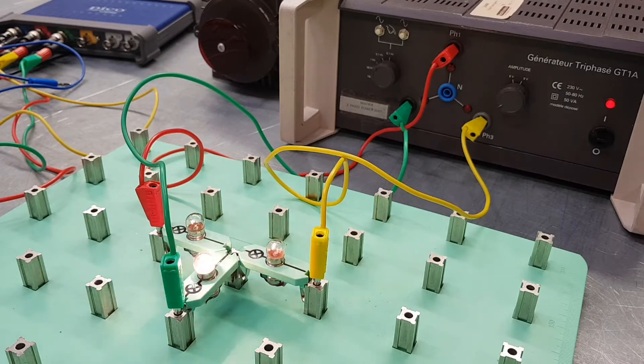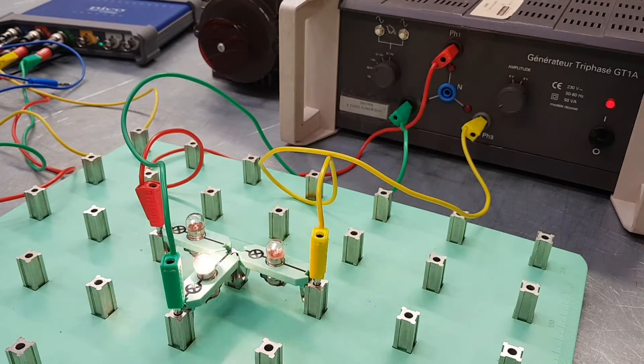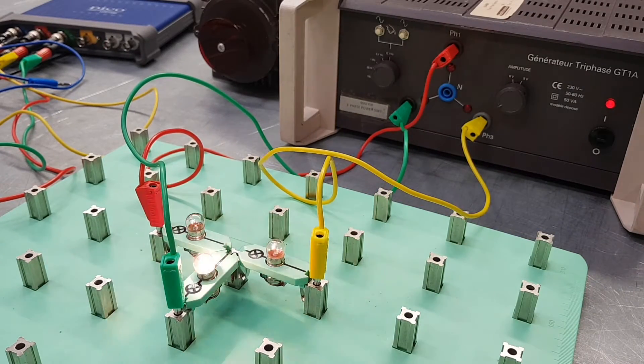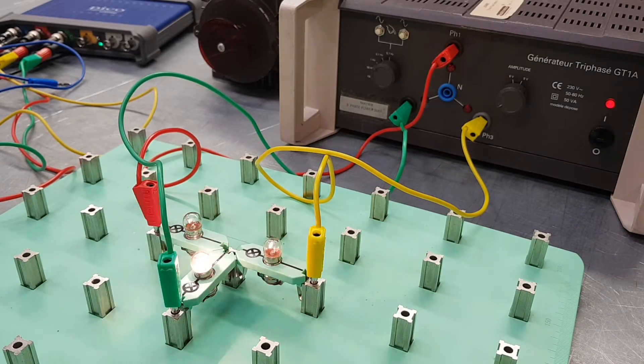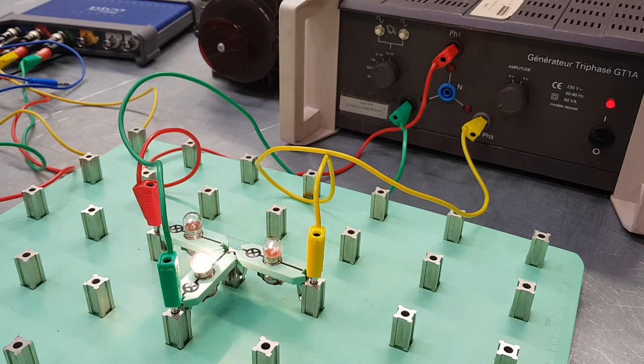Another thing you might notice is there's no neutral connection. That'll be explained in more depth in a future video, but if you've got a balanced load, you don't need a three-phase neutral connection. We've got three lamps here of equal power, so no neutral connection is required at all.